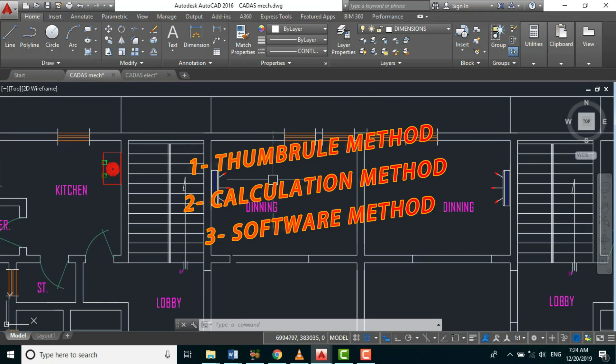The thumb rule method is an approximation method where we consider the room or space area and the occupancy level. We have three multipliers for sizing our AC. The first is multiplying our space area by 0.07, which is used for corridors, lounges, and walkways — this gives us the tonnage requirement.